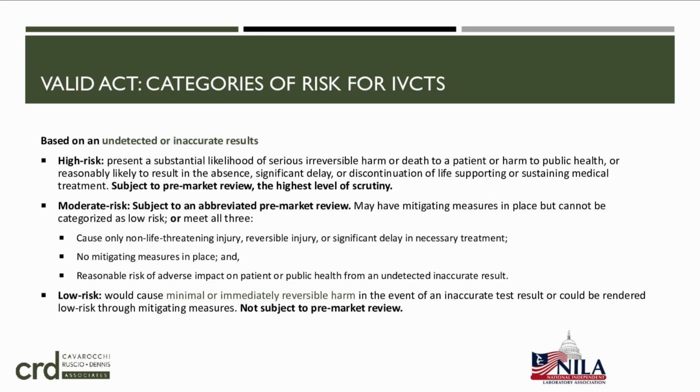And then finally, a low risk test is any test that would cause minimal or immediately reversible harm in the event of an inaccurate test result. Or it could be rendered low risk through mitigating measures, which would be in place up front. Low risk tests are not subject to pre-market review. They would only be subject to that registration and listing that I mentioned previously.